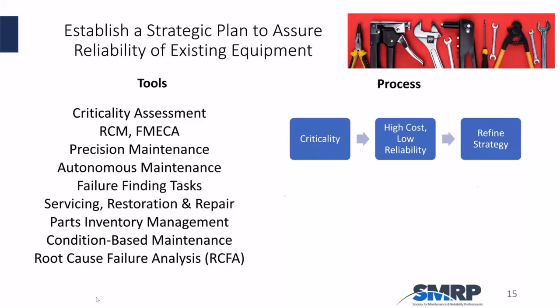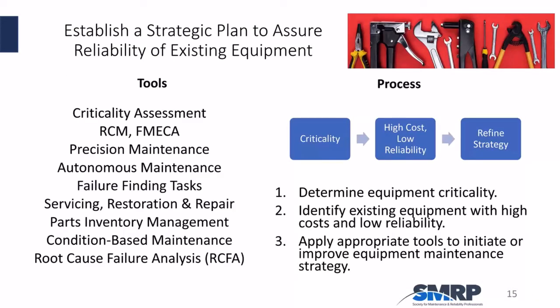So precision maintenance is really about making sure that whatever maintenance function we're doing, we're using the best practice. Things like properly tensioning belts on a pulley and belt system, making sure we have precision alignment using laser alignment gear, accounting for thermal growth in the housings of the motor and driven equipment, using good, clean lubricants, and using things like ultrasound lube caddies to make sure we're adding just the proper amount of grease to bearings.